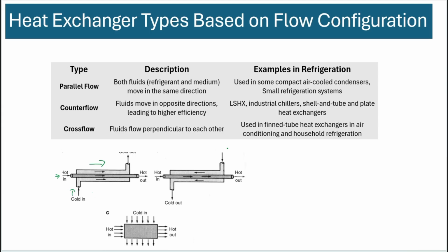Crossflow is extremely common in evaporators and condensers where you have to cool the refrigerant using air. The fin tube heat exchangers used in air conditioning and household refrigeration are almost always in cross-flow configuration.